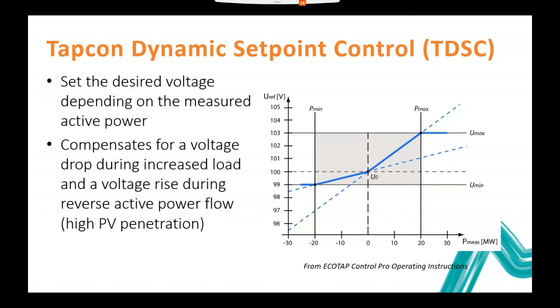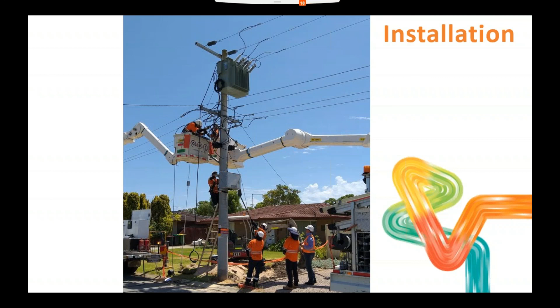You can see the pretty standard pole top transformer on top with a control cubicle where the guy with the ladder is, with the RTUs in there as well. So Western Power actually opted for the SCADA. We've got it coming back to our control center, and we're also taking all the data into our historian databases. And this is some very preliminary results because we only recently installed these.